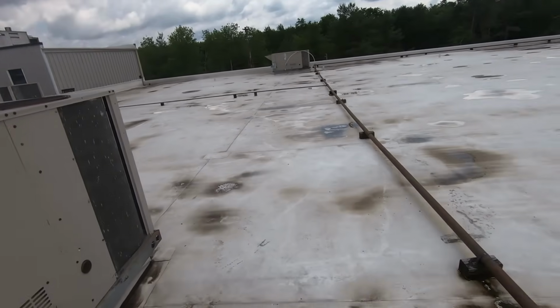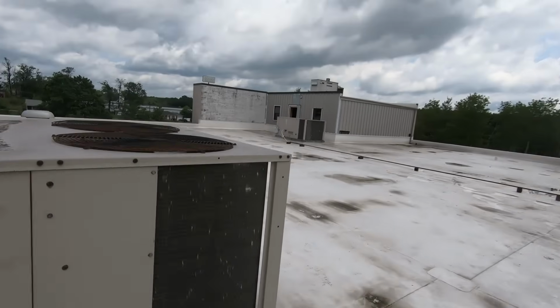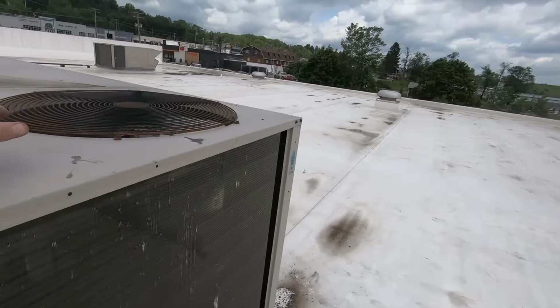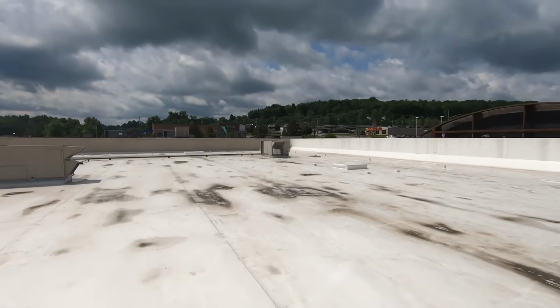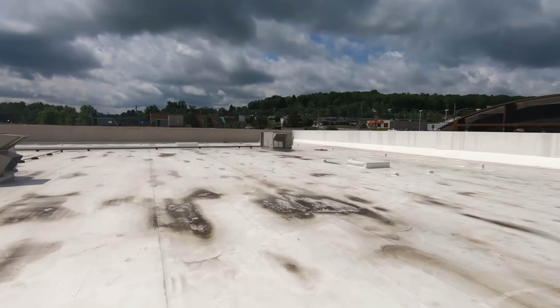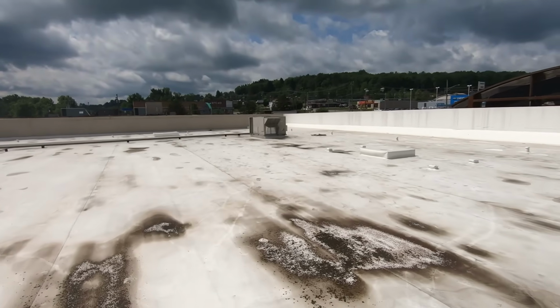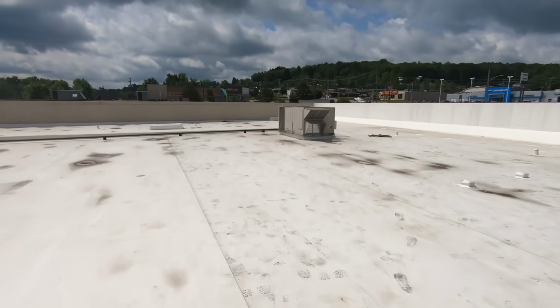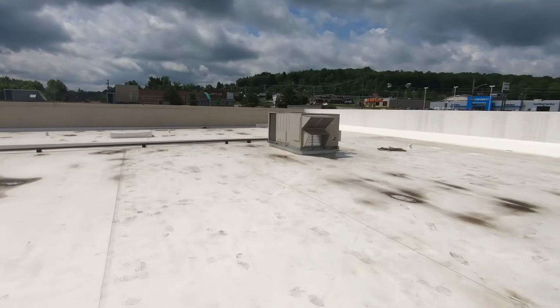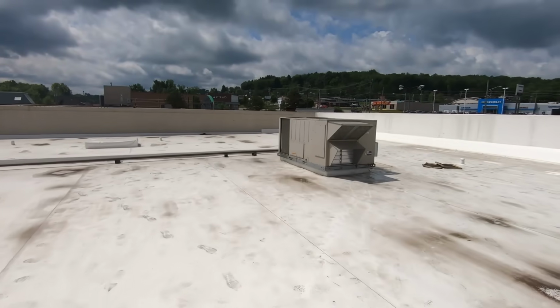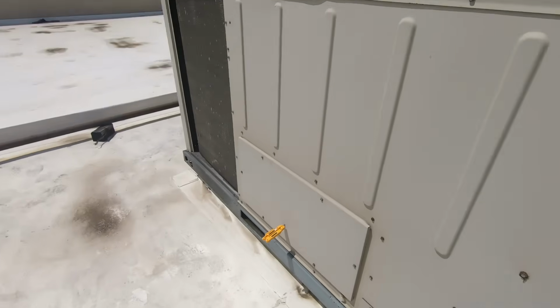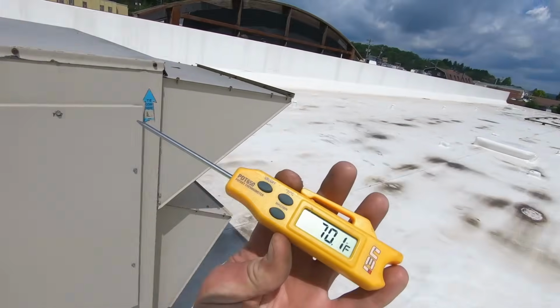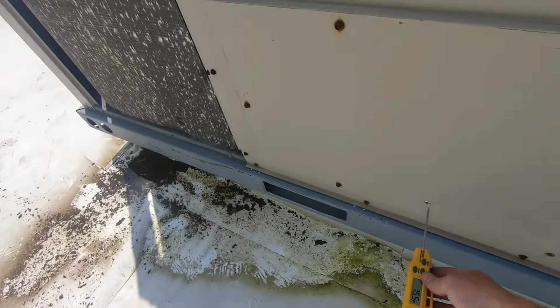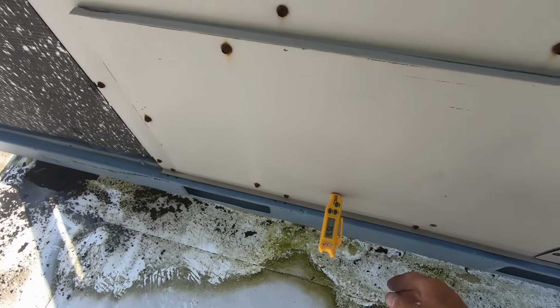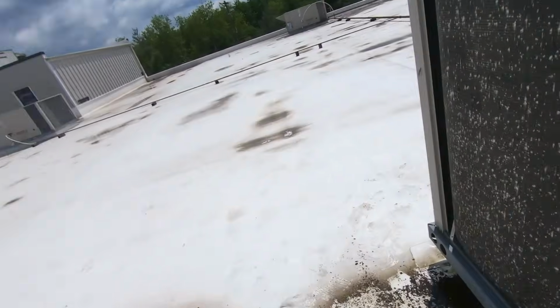Well, I'm gonna take my gauges off of that one. Suction line felt cold right off the bat. And I forgot my temperature probe over here. Again, these are the most lost tool that I have, these UEI temperature probes. So if you've ever found one on a roof in the Pittsburgh, Cleveland area, there's a good possibility it was mine. Yoink, 70 degrees. Yeah, we'll see what that's doing here in a minute.